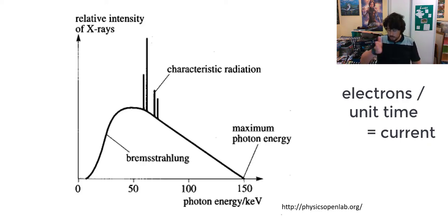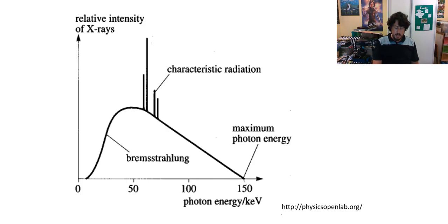So rather than just increasing the voltage across the x-ray tube, we're going to change the current. So we're going to change the amount of electrons crossing the tube.